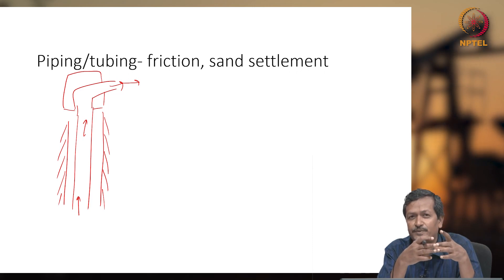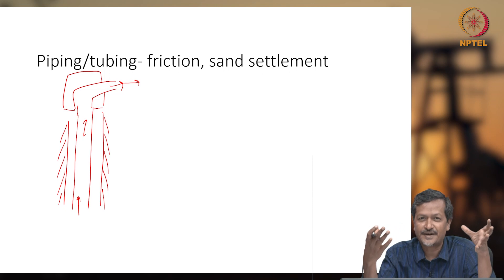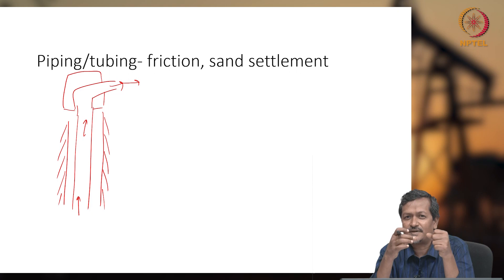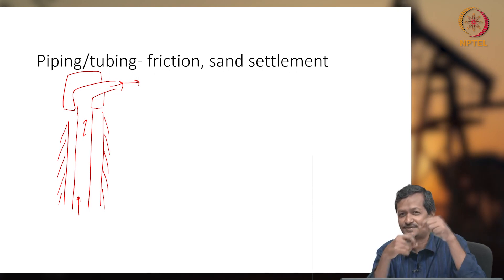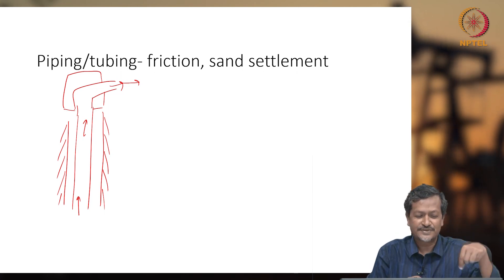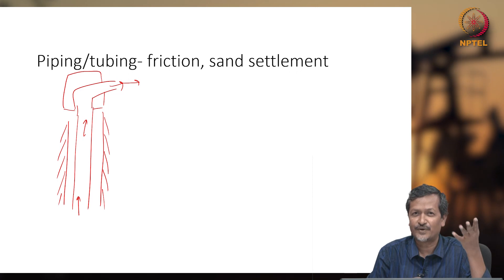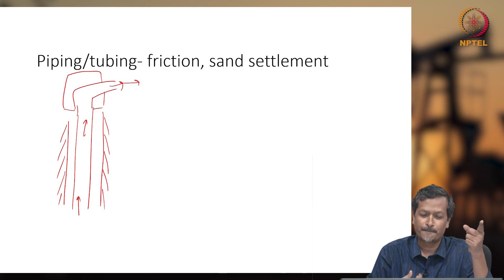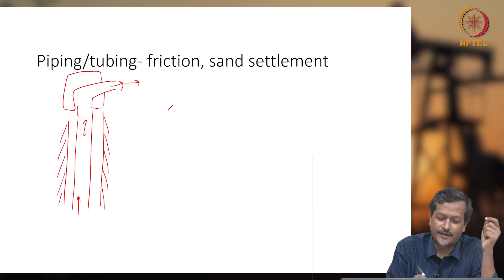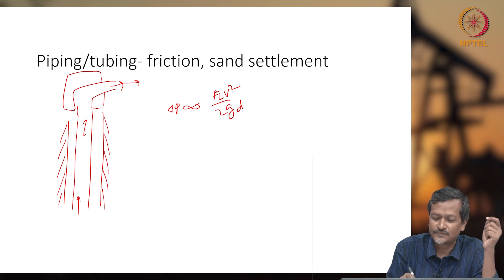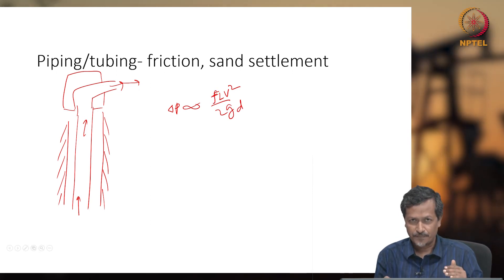All these things are pipes. How do you design a pipe — whether you select a 1-inch pipe or 10-inch pipe? What is the criteria? If you select a very narrow pipe, like a straw for drinking mango juice, can you use that for oil and gas production? You could, but the issue is that it will give very high friction. The pressure drop through the pipe is given by: ΔP = f · L · V² / (2 · g · D), where ΔP is the pressure drop through the pipe.